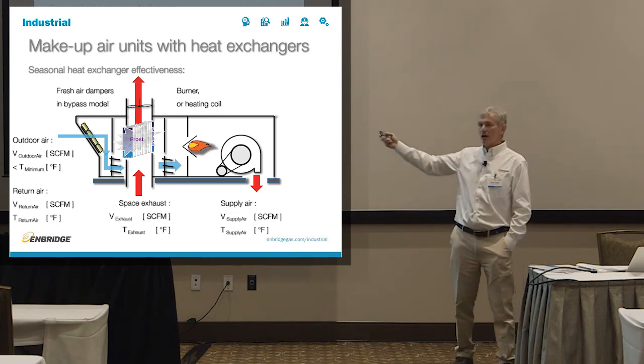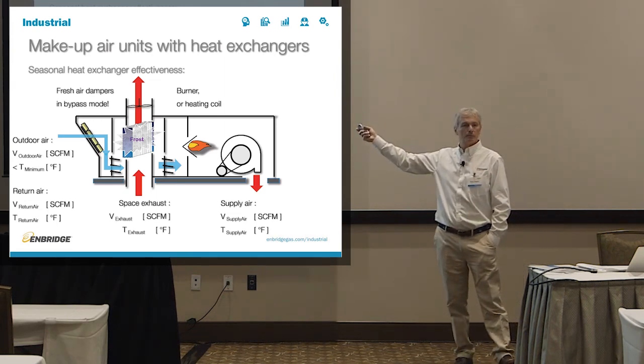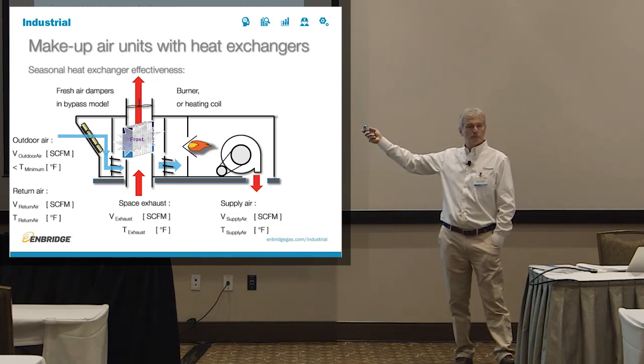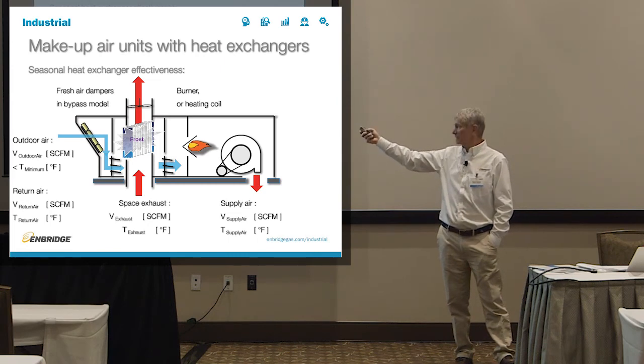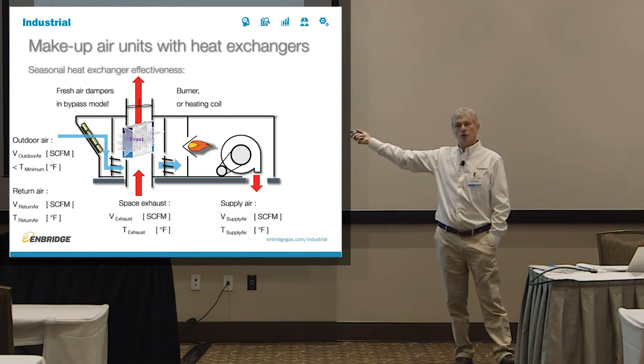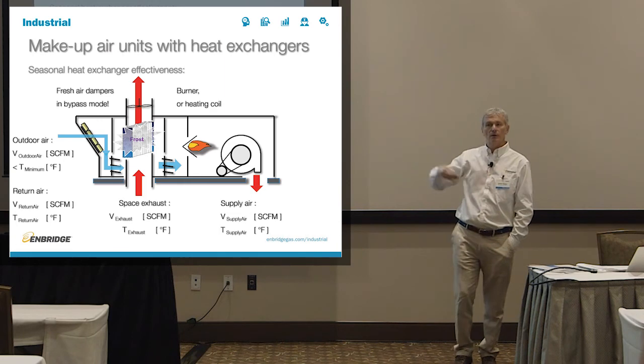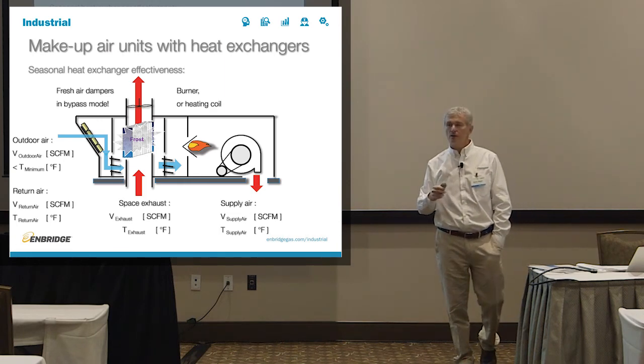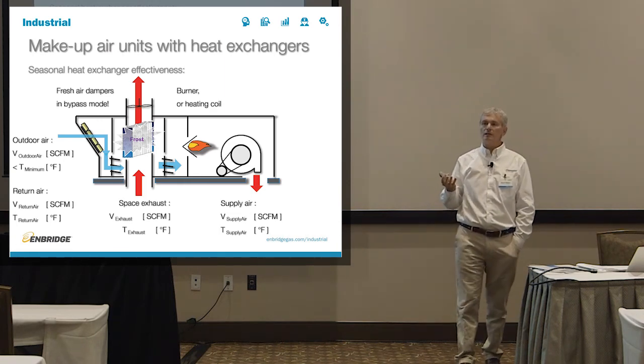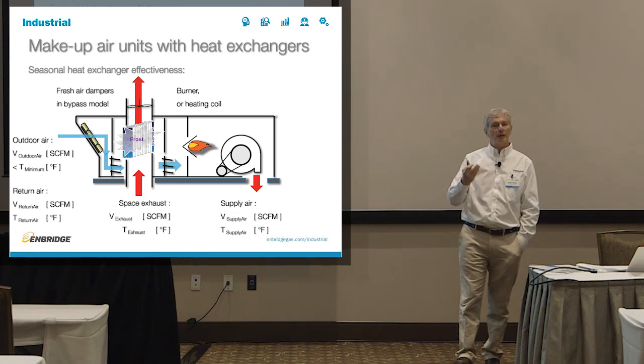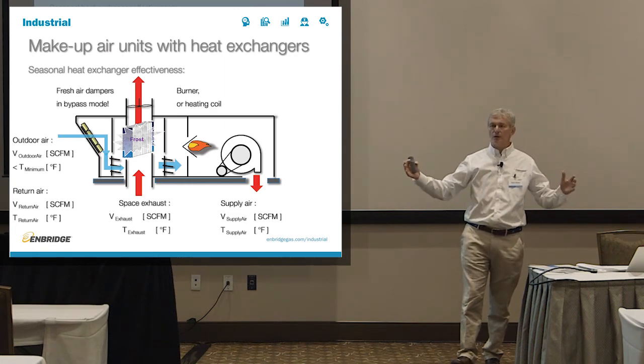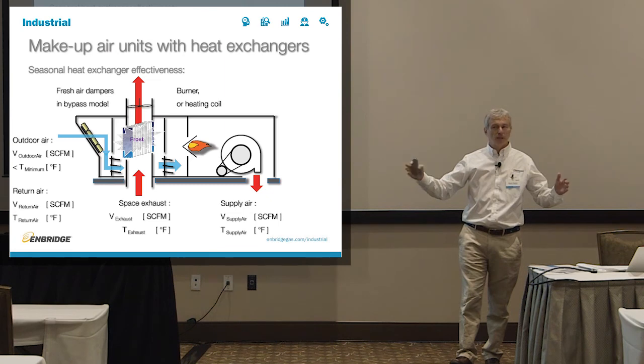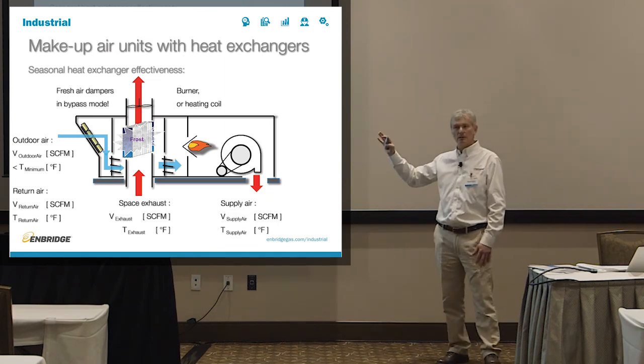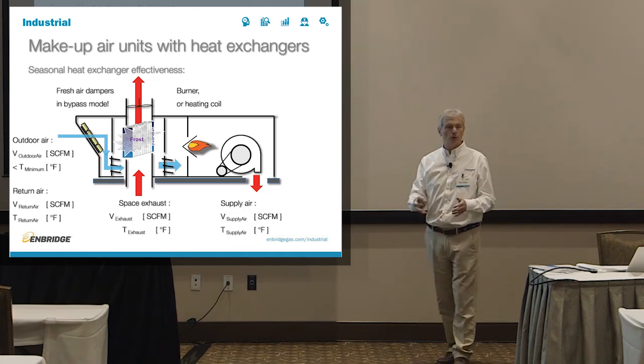So the question now is, how many hours a year will that happen? I had one vendor who says that every time the outdoor temperature is below 36 degrees F, they will go into some sort of reduced amount of heat recovery. That's a significant portion of the heating season. So now your payback time starts to spread out. And this is not a bad thing, this happens, but you have to be aware before you install the unit.